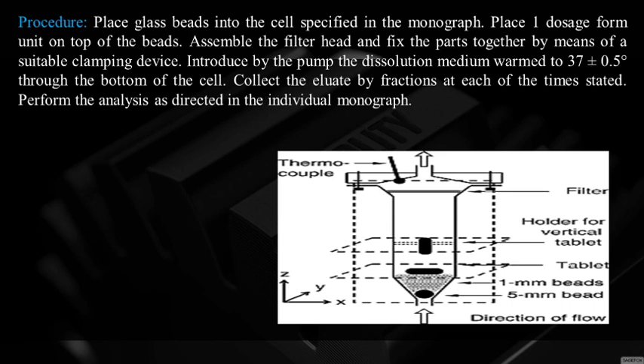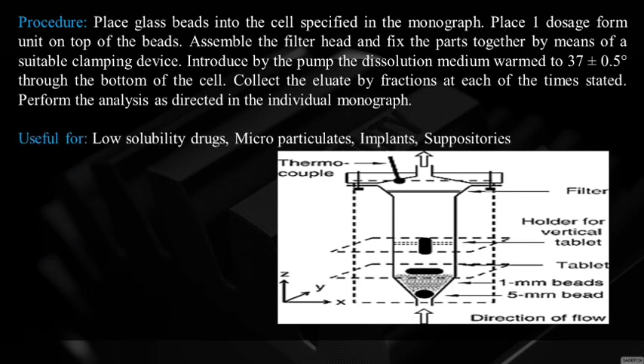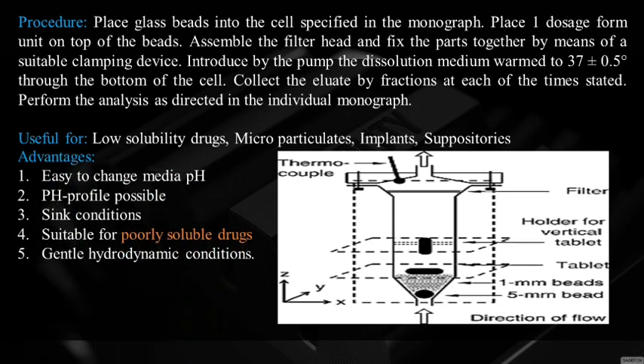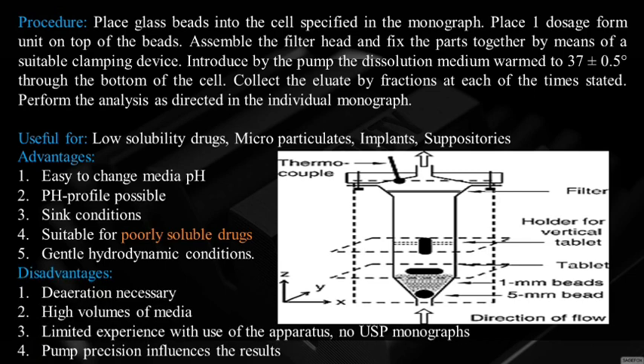Procedure: place glass beads into the cell, place one dosage unit on top of the beads, assemble the filter head and clamp. Pump dissolution medium warmed at 37 ± 0.5°C through the bottom of the cell. Collect eluates by fraction at each stated time. A 5 mm bead is placed at the bottom, then 1 mm beads, with the tablet held vertically. Useful for low-solubility drugs, microparticulates, implants, and suppositories. Advantages: easy media change, pH profile possible, suitable for poorly soluble drugs. Disadvantages: deaeration necessary, high media volume, limited experience, no USP monographs, pump precision influences results.